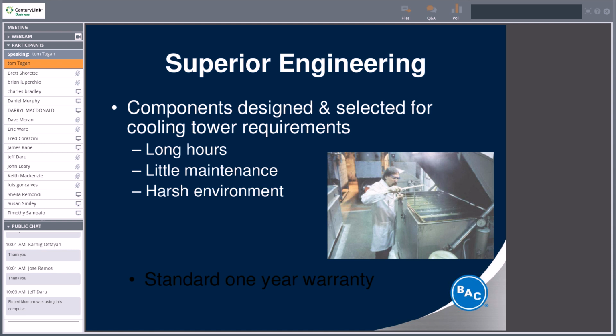Superior engineering, you'll see this slide on any manufacturer. I can tell you right now, the big 3 cooling tower manufacturers that you probably have on your building all spend a ton of money on research and development, trying to provide the most efficient, most cost-effective, longest-lasting product on the market. Most of our equipment has a standard 1-year warranty on the tower itself. You have that 5-year drive shaft or mechanical drive system warranty, including the motor. When you go to a stainless steel cold water basin, which we highly recommend, you get a 5-year leak-proof warranty there. It's a welded basin. They basically fill it with water and test it after the weld during the manufacturing process.